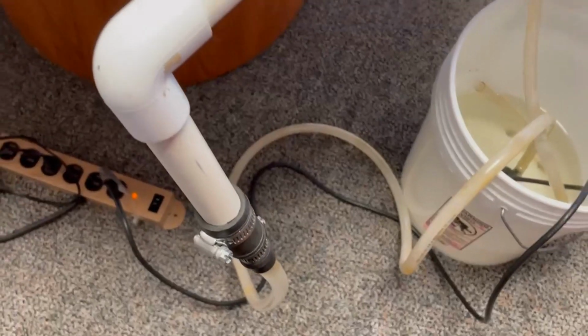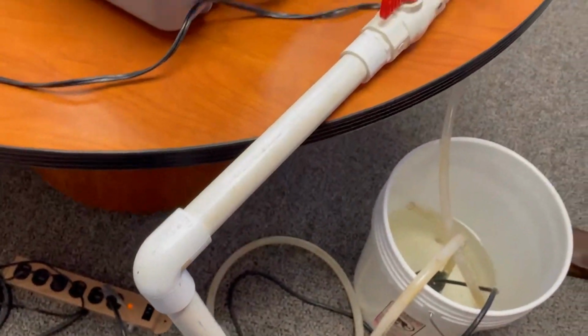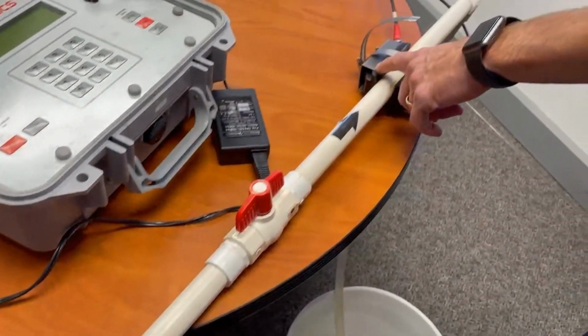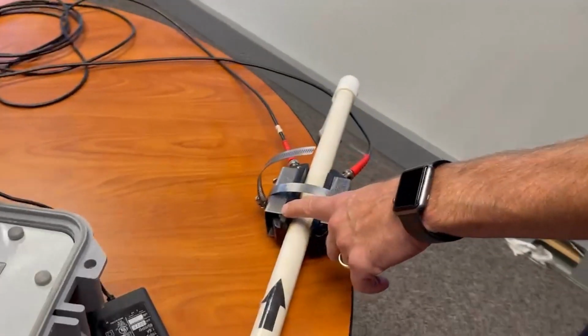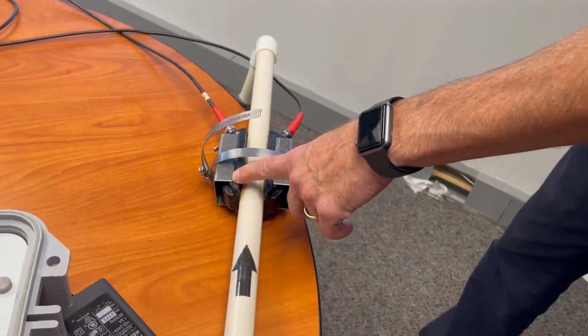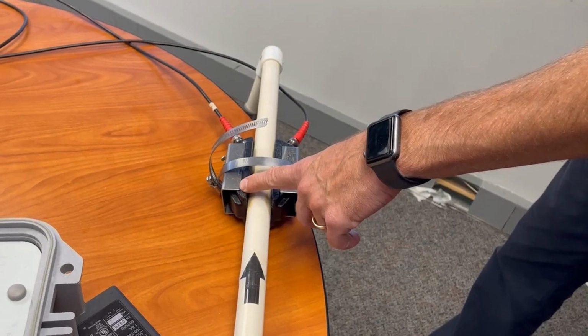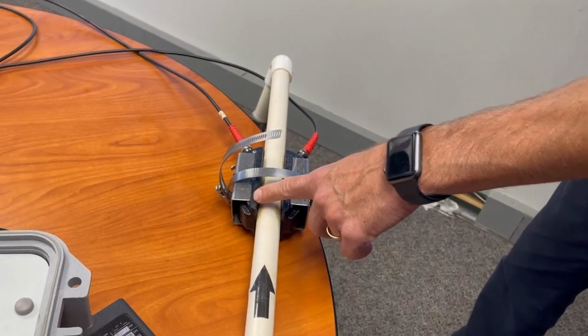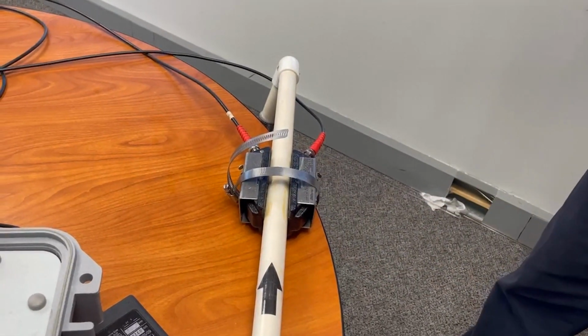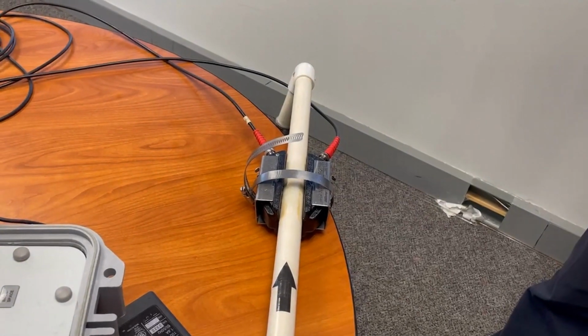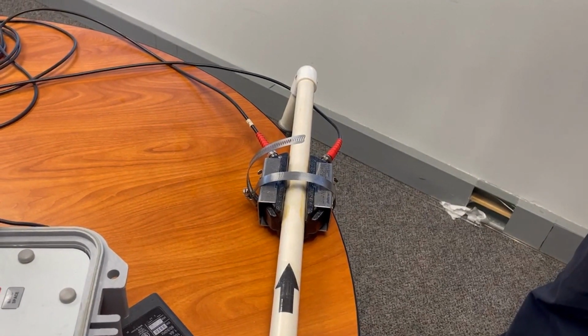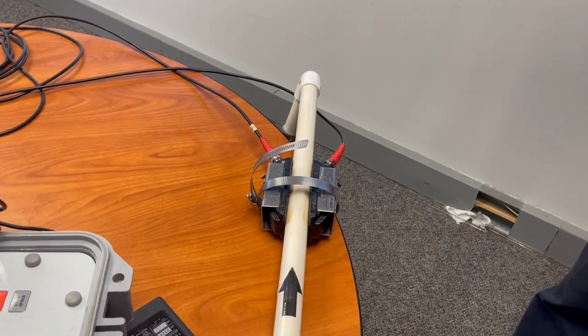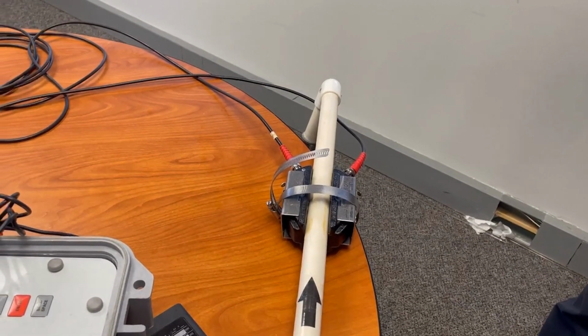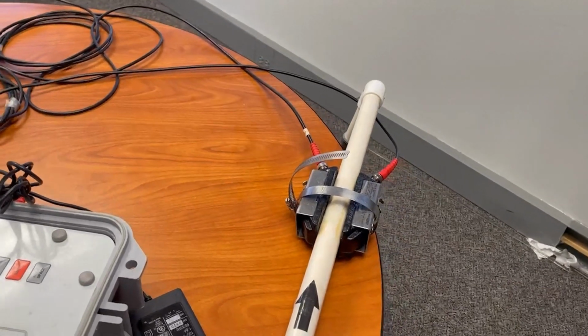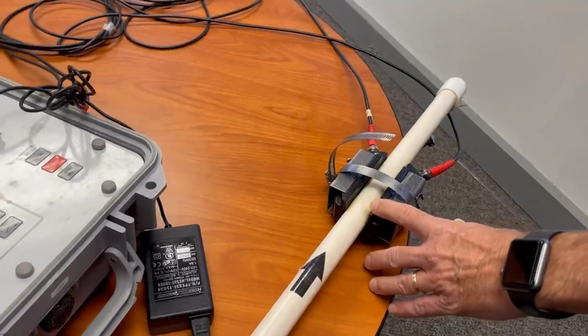So this transducer emits an ultrasonic sound wave by emitting an ultrasonic beam into the stream flowing in the pipe. Sound waves are reflected back to the sensor from particles or bubbles present in the flowing material. The motion of particles shifts the frequency of the beam, which is received by the second transducer on the opposite side of the pipe.